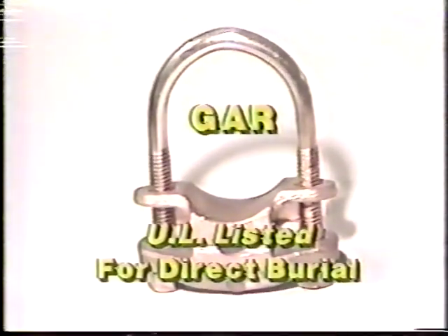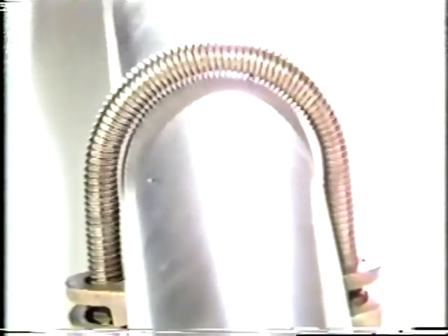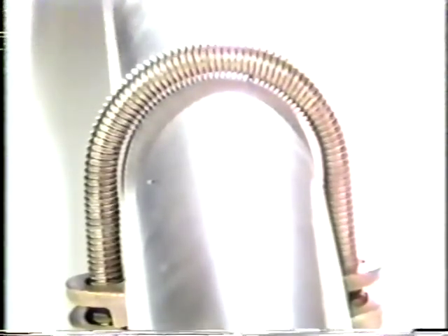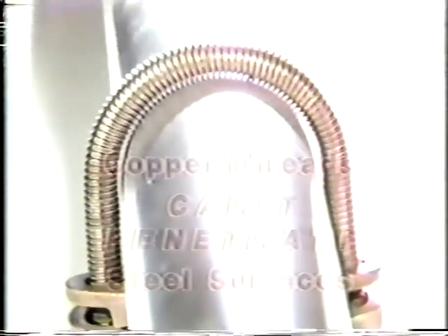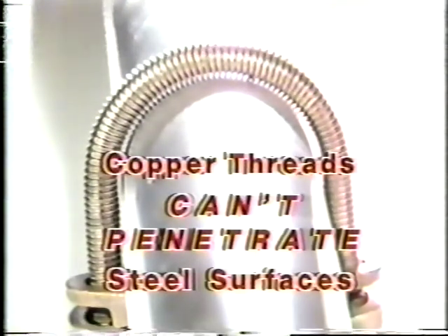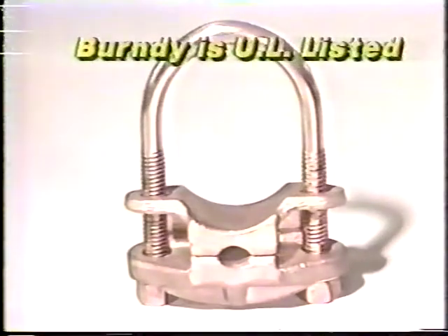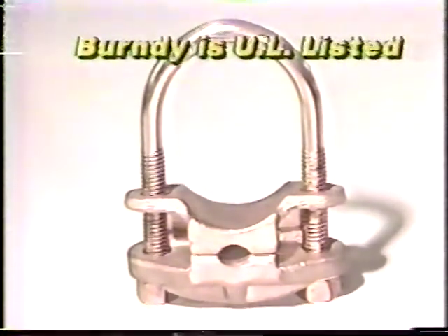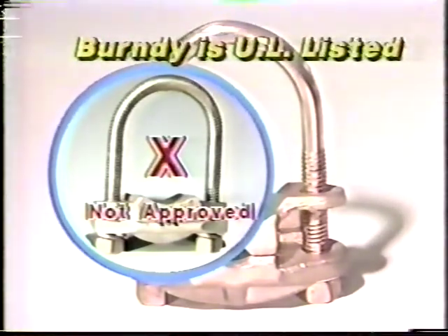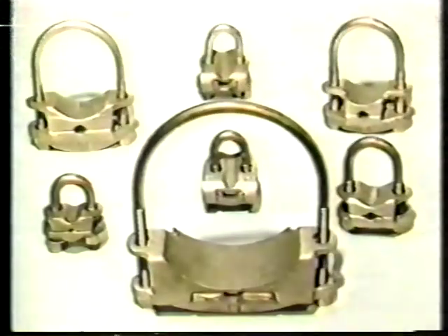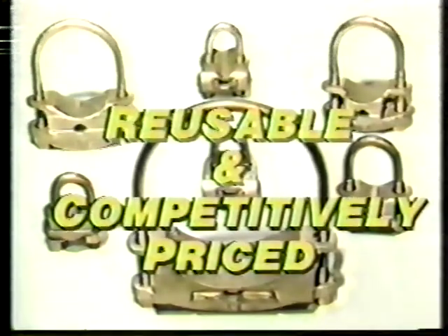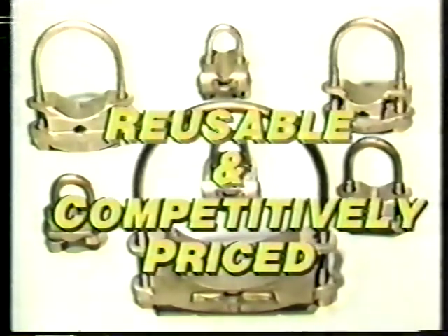Don't be confused by competitive claims that threaded surfaces bite into the steel pipe. Conductive copper alloys are much softer and can't penetrate a steel surface. Superior connection is the result of a greater conductive surface area. That's why Burndy connectors are UL listed for direct burial, and other clamps are just not approved. In addition, Burndy GARs are reusable and competitively priced. Why pay more for less quality?